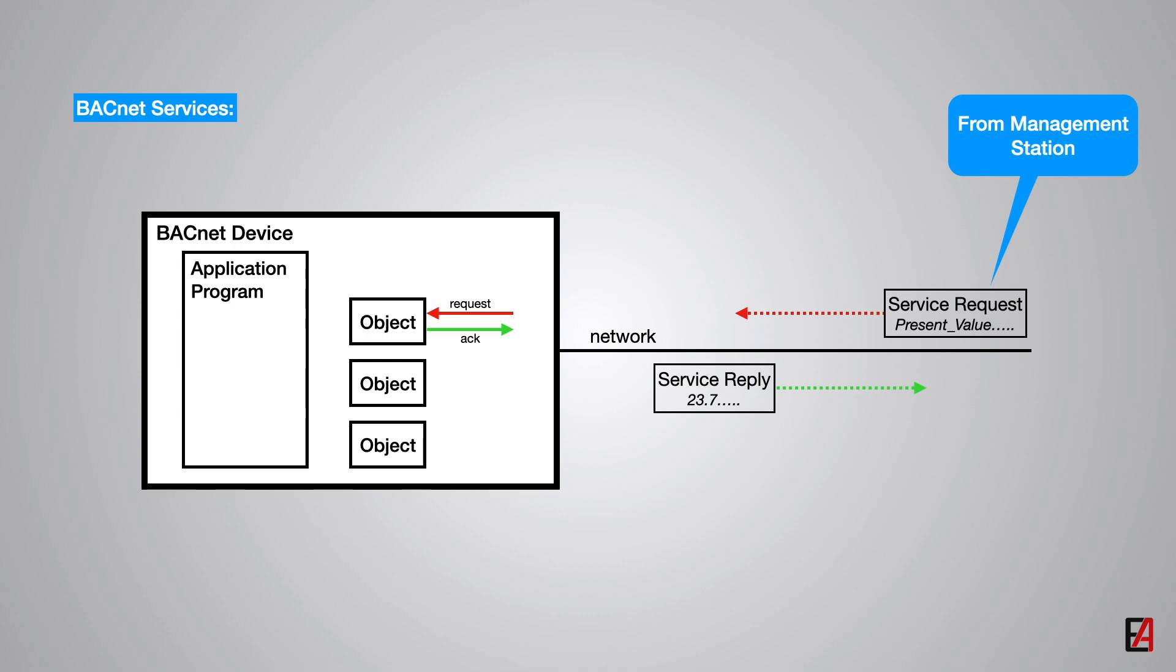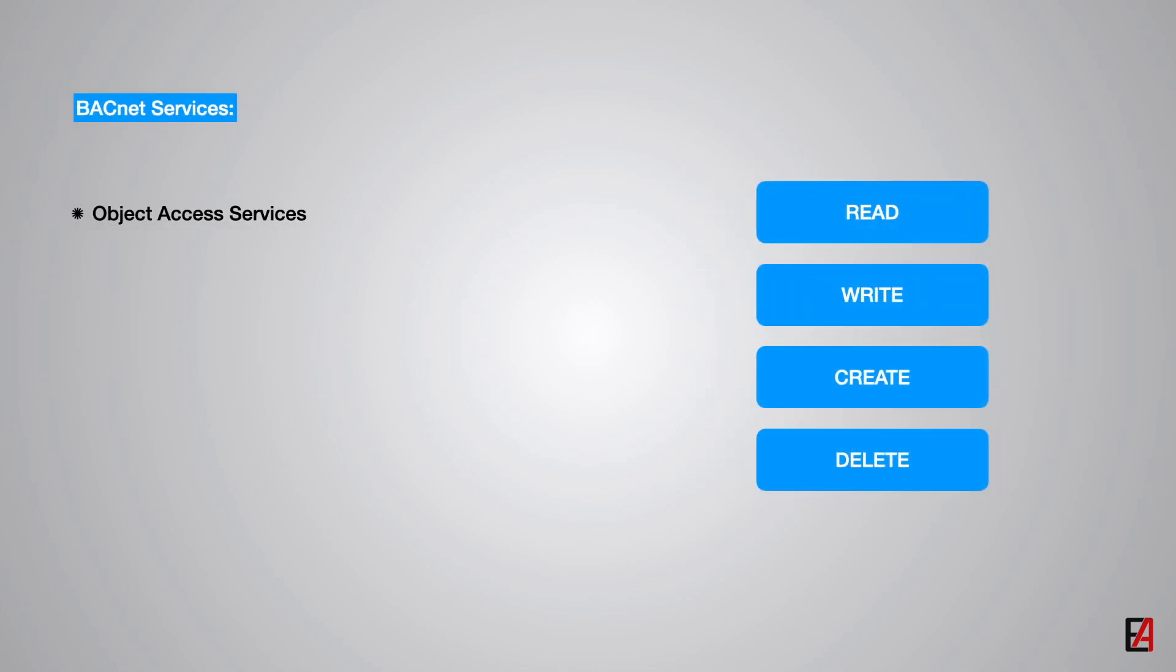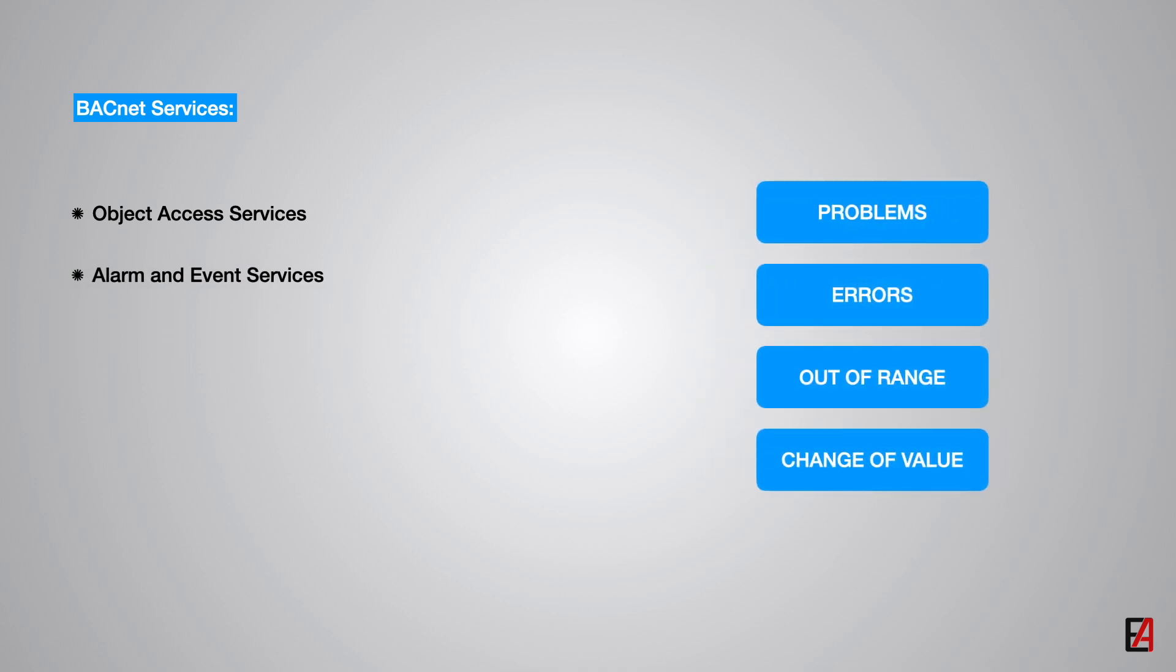An application program running on the BACnet device issues service requests and processes them upon receipt. BACnet defines 32 services and classifies them into five categories. The object access services provides the means to read, modify and write properties and to delete or add objects.